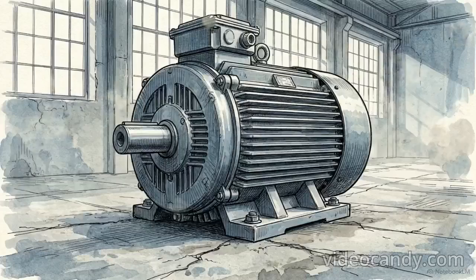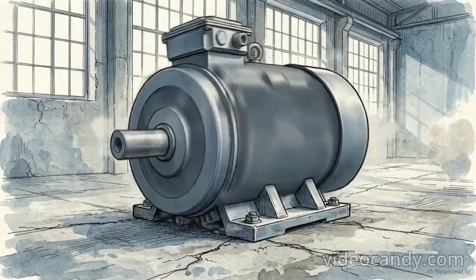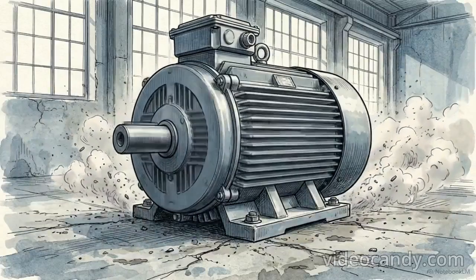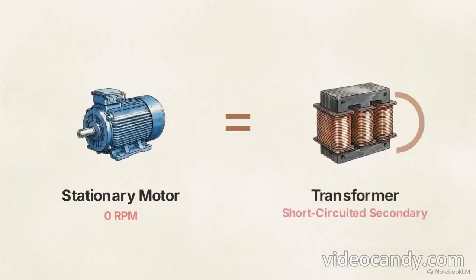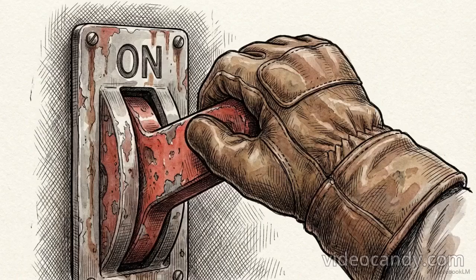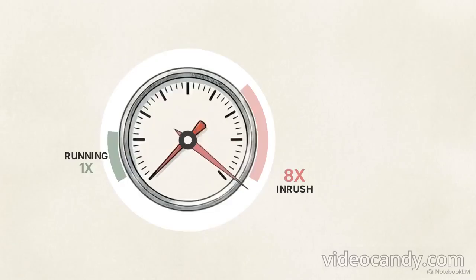When an industrial induction motor is at a standstill, at exactly 0 RPM, it does not behave like a motor. To the electrical grid, a stationary motor is effectively a transformer with a short-circuited secondary coil. Connecting a load of this size directly to full grid voltage, a method known as direct online starting, forces the motor to draw an immediate inrush current that is 7 to 8 times its normal running load. This massive spike in amperage generates extreme internal heat.